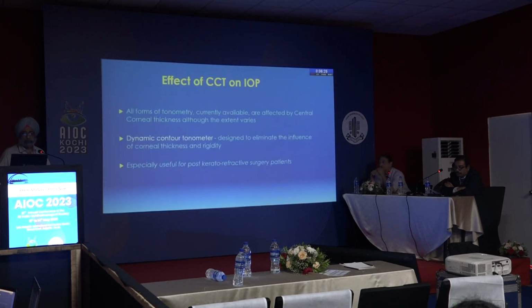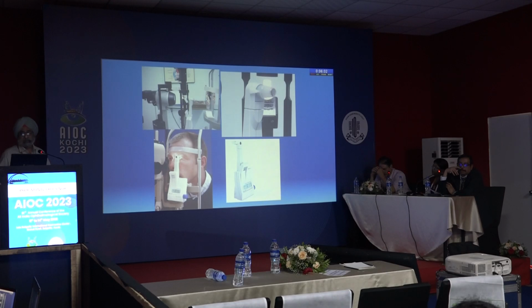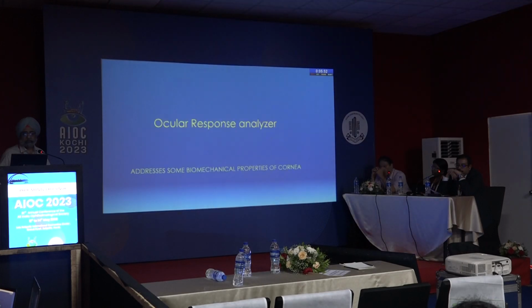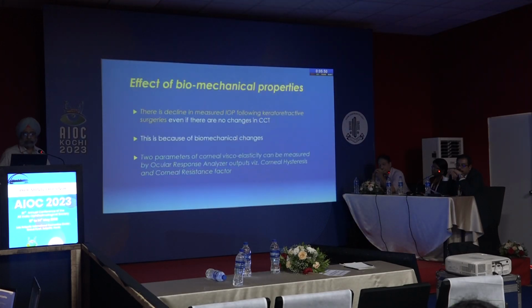Pascal dynamic contour tonometer. Actually, in fact, we know that all forms of tonometry currently available are affected by central corneal thickness, although the extent varies. So this DCT was designed to eliminate the influence of corneal thickness and rigidity, especially for post-keratorefractive surgery cases. It's especially useful for keratorefractive surgery, therefore, but it's expensive. There is a running expenditure, and it takes a lot of time to use, so it has not become very popular.